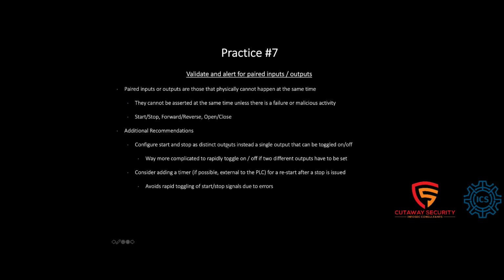In this practice, we also added a couple other ancillary support recommendations. So one is to configure distinct outputs, if possible, instead of just one, to an MCC, the motor control center, for a start-stop. If you have a start for the motor and a separate stop for the motor, it's much more difficult for the attacker to manipulate both of them to rapidly toggle on and off, versus just one register, one output going to the MCC. Then it's easy to toggle on and off, right? So if you have two separate ones, it's much more difficult, but that needs the MCC to support those two outputs, and you have a physical cable or some kind of communication for two outputs to the MCC.